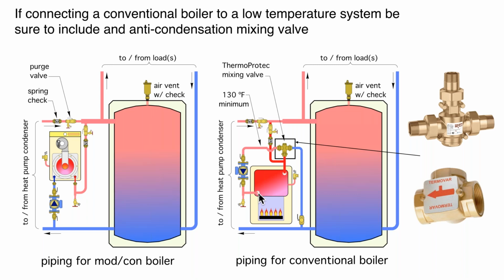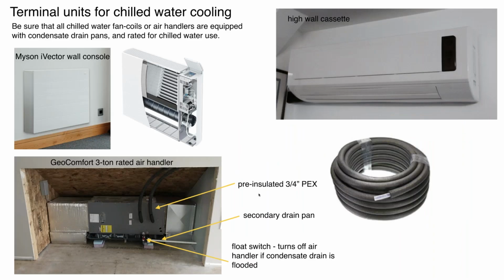Chilled water cooling, you can do it with wall-mounted fan coils like this. Here's a 3-ton. This is a GeoComfort air handler. This is 3/4-inch pre-insulated PEX that's bringing the chilled water to the coil. Okay, so we've got a central duct system here that does single zone cooling in the building. I like the 3/4-inch pre-insulated PEX. It's fairly easy to run it through, and you don't worry about condensation because of having somebody not glue the joints and the insulation together.